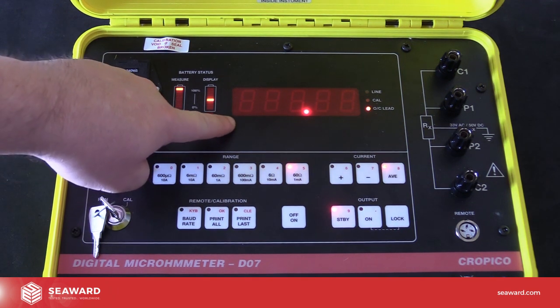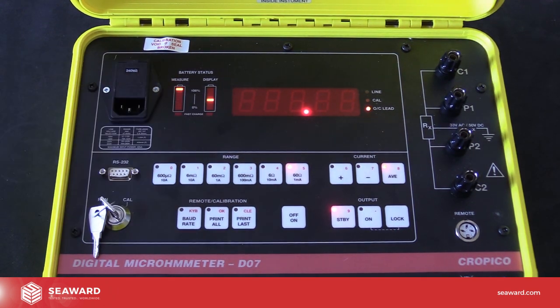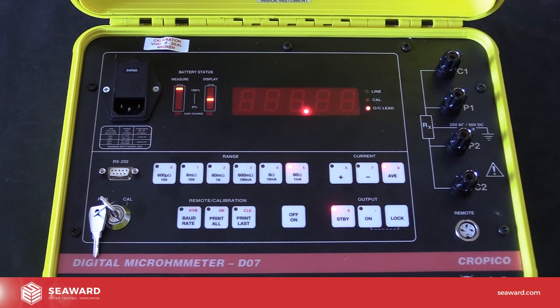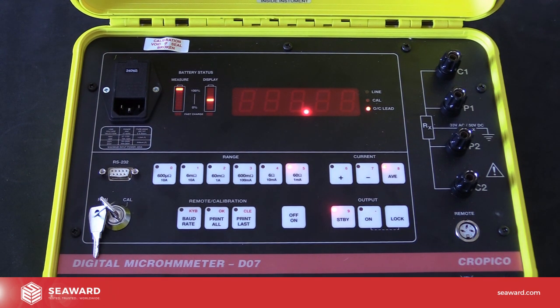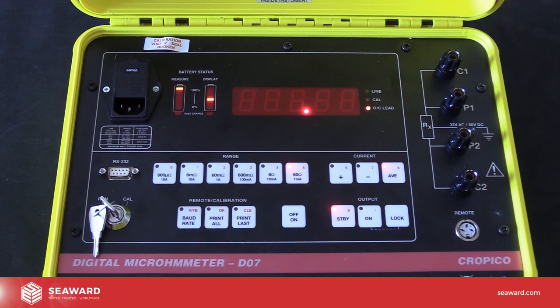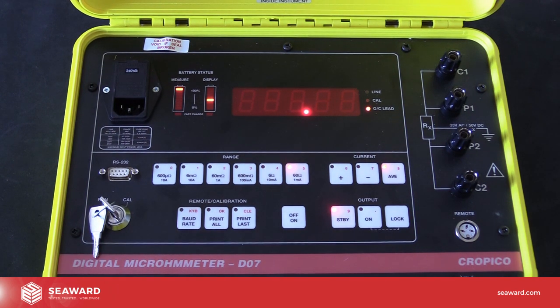A large 7-segment display gives the user the readings, and you'll notice there are a number of LEDs indicating the status of the device at all times. So firstly, let's have a look at the test connections point. As with all of the Cropico ohmmeters within the Seaward range, we use the 4-wire or Kelvin method for connections, giving you optimal measuring accuracy when performing your low resistance checks.